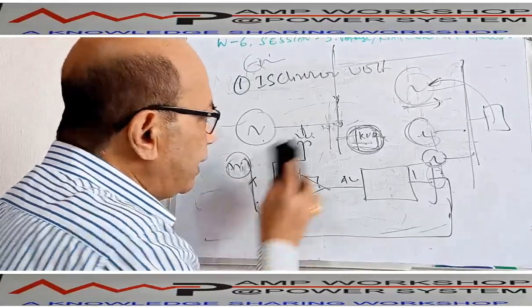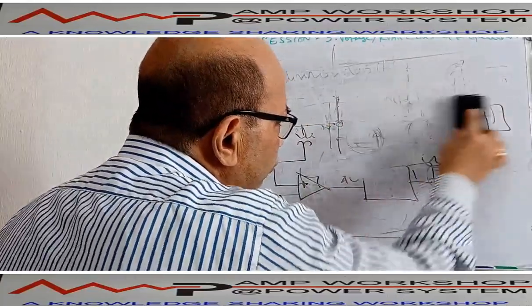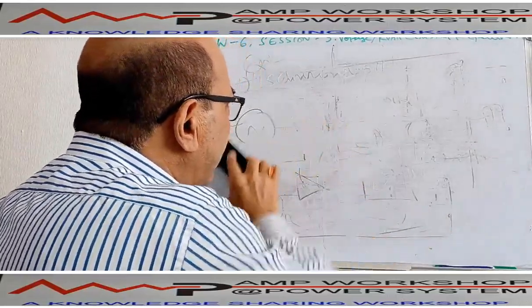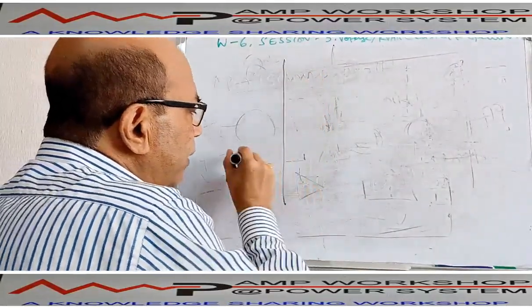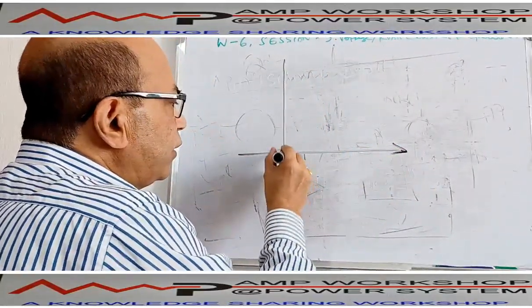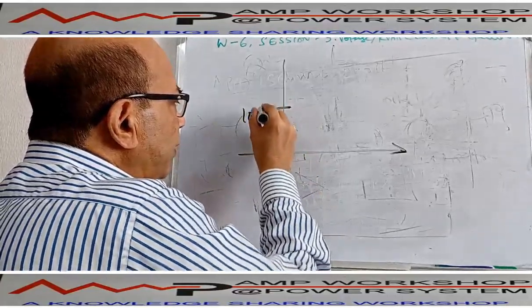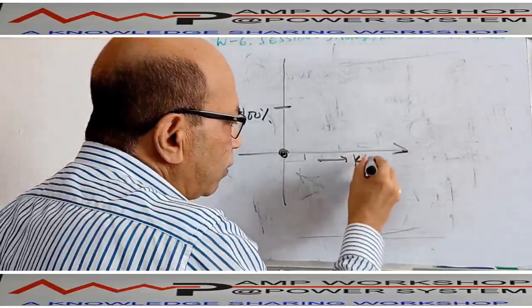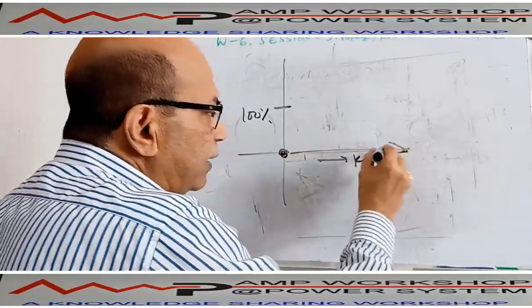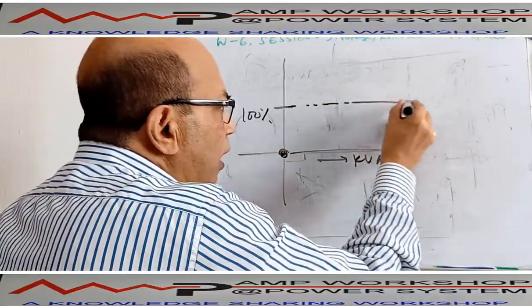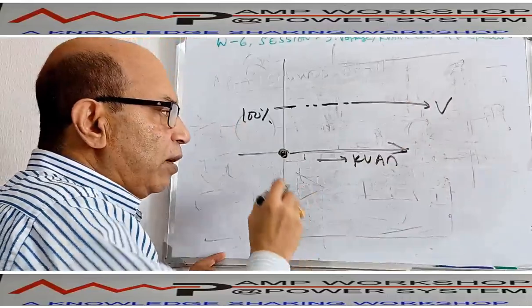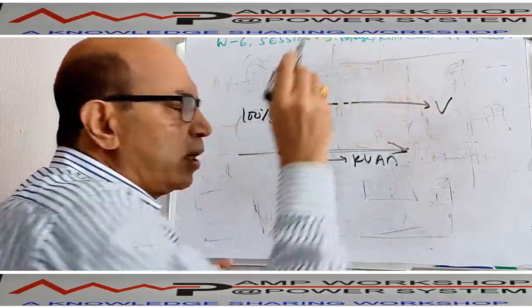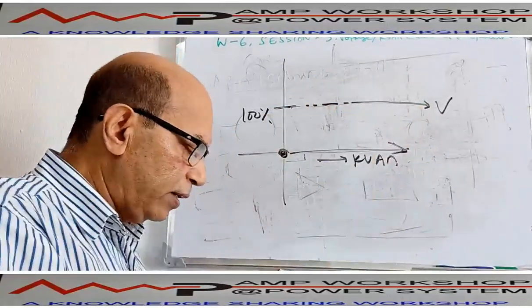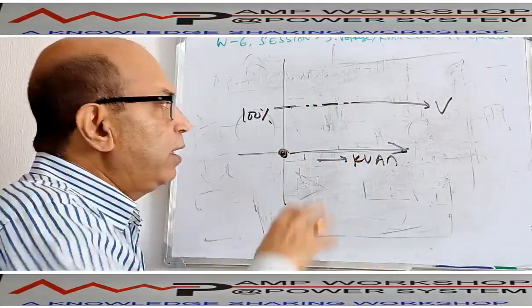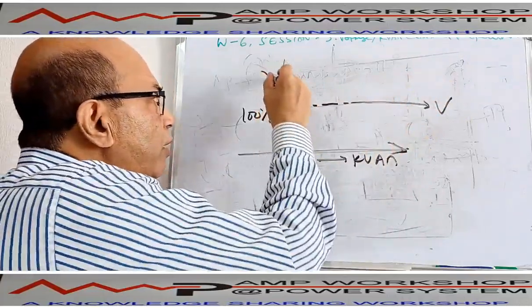Now the second mode of operation. If you draw the isochronous mode characteristics, voltage versus KVAR load, the diagram will be a straight line. Suppose this is your 100% voltage, and this side is the KVAR load on the machine. As you keep increasing the KVAR, the voltage will not change. This is the voltage characteristic of the machine. As you increase the KVAR, the voltage will be maintained. If this is the characteristic, we call it an isochronous characteristic. With KVAR loading, the voltage of the machine will not change.